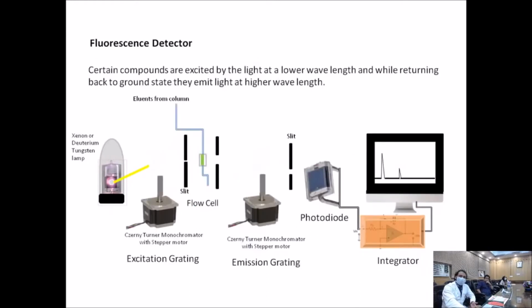Based on the fluorescence type detector, a certain compound will be excited at a lower wavelength, and while returning to the ground state, it will emit light at a higher wavelength. Based on the excitation and emission wavelength, it can have more sensitivity compared to ultraviolet detection.